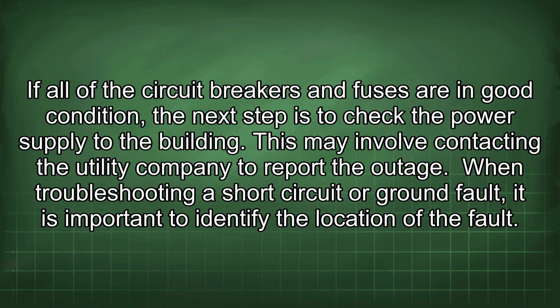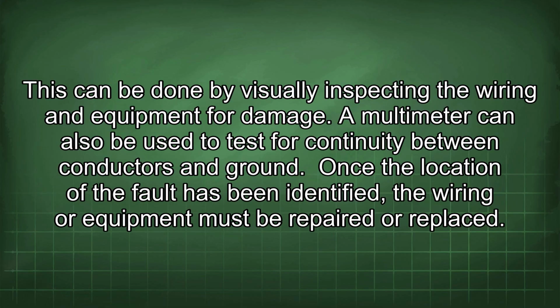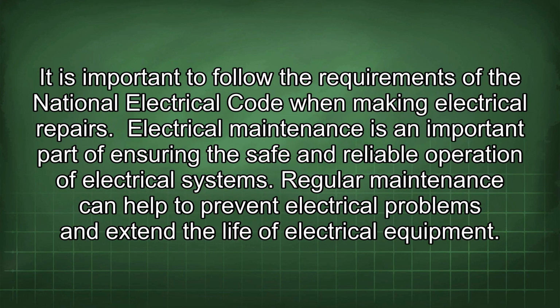This may involve contacting the utility company to report the outage. When troubleshooting a short circuit or ground fault, it is important to identify the location of the fault. This can be done by visually inspecting the wiring and equipment for damage. A multimeter can also be used to test for continuity between conductors and ground. Once the location of the fault has been identified, the wiring or equipment must be repaired or replaced. It is important to follow the requirements of the National Electrical Code when making electrical repairs.